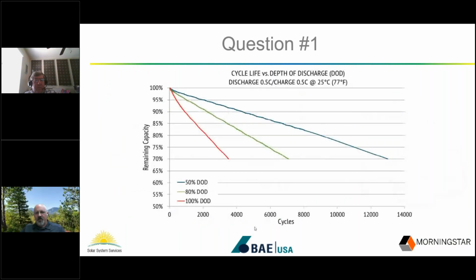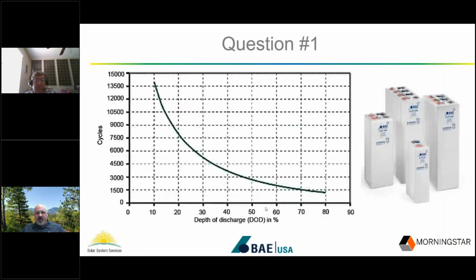One thing I wanted to bring up—Rob and I had talked about this prior to the webinar—you'll notice the graph stops at 80%. An important point I want to make is that when you're looking at a quality lead acid battery like the BAE, our data sheet ratings are all based on that 80% DoD. So in many cases, from a layman's perspective, if it's on the data sheet, that's the amount of capacity you can use out of the battery. From a technical standpoint, that's 80% of your capacity, but I want to be clear that doesn't mean you can only use 80% of that rated capacity. What's on the data sheet is actually the usable capacity of the battery.